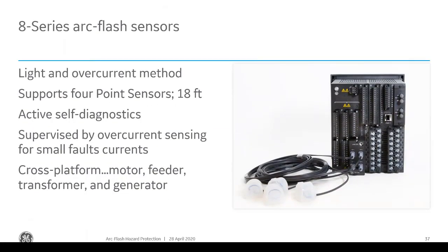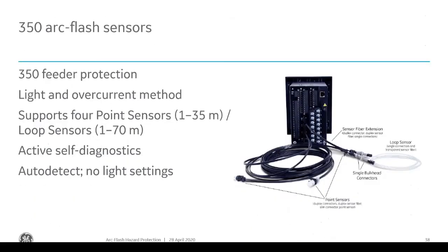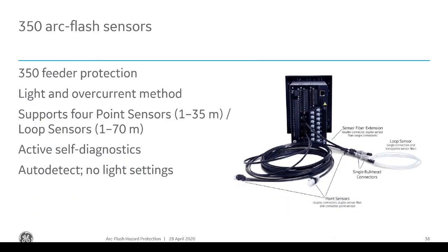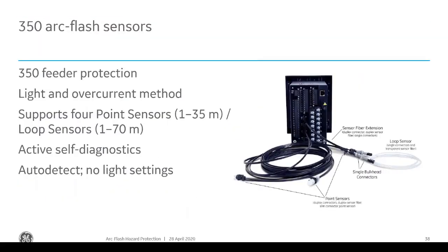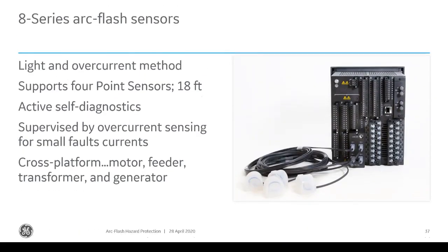We have different types of sensors. Most of our relays have up to 3 to 4 arc flash light sensors. So we have the point sensors, which can go up to about 18 feet. They could be used for anything: switchgear, motors, transformers, generators. Then we have another relay, the 350, which is similar, but it also includes loop sensors. So with loop sensors, you could loop it into the switchgear, so you can cover multiple lineups with one sensor. The point sensors can only cover where that point sensor is located, right?